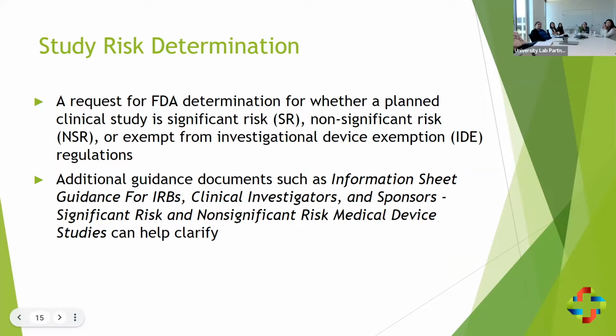And so is it safe to investigate in humans without getting the full IDE process or approval from FDA? The investigational device exemption is usually a clinical study, a large packet of information goes to FDA, and they have to review it and approve it within 30 days. But you can go to FDA ahead of time in this pre-submission and do the study risk determination submission and ask them, and they will come back with a 1 or 2 page document that says, yeah, we've looked at it and you're non-significant risk, do not submit an IDE to us. Or they'll say, yeah, this is significant risk, here are the reasons why, and this is why you need an IDE.